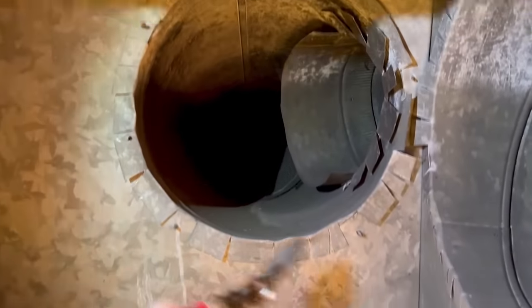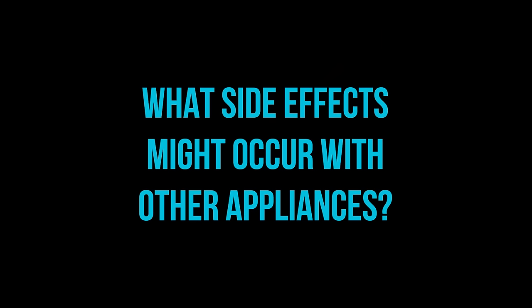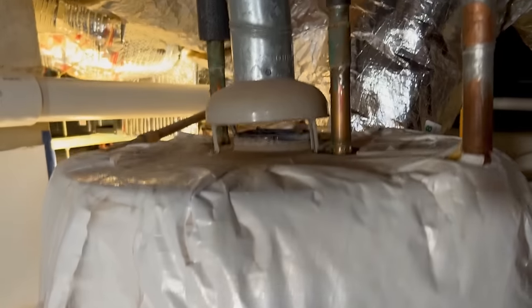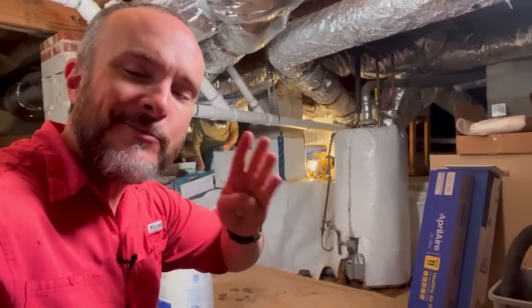We're going to seal everything and wrap it with bubble wrap — we don't use fiberglass insulation. When you're doing an HVAC replacement with a water heater involved, you want to be aware that you may be orphaning the water heater. But since this unit was already a high-efficiency furnace, we're not worried about orphaning because it already happened. You can see this water heater is now the only thing warming up the entire chimney, and we know it's not a problem because we already tested for it.